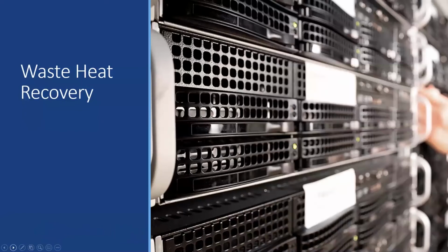Waste heat recovery. In addition to reviewing your primary sources of comfort heat, you can use supplemental heat through waste heat recovery within your facility. Waste heat is a result of various facility equipment outputs, from, but not limited to, annealing furnaces. You could have server rooms producing heat, air compressor rooms produce heat. Recovering this heat can supplement your comfort heating and thus support cost savings, as well as reduce environmental impact. This can be for any size facility to take advantage of.